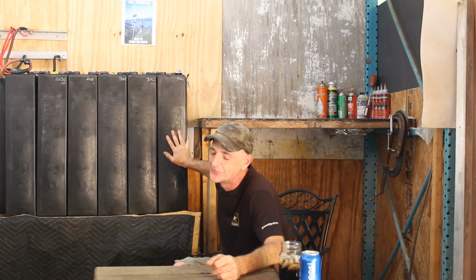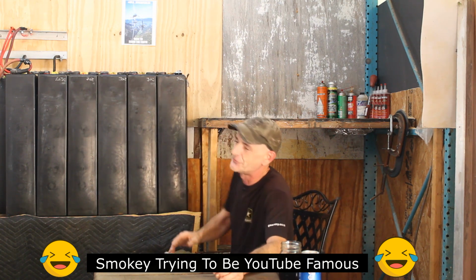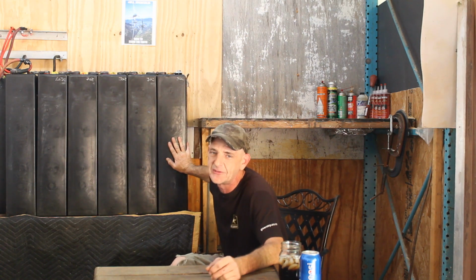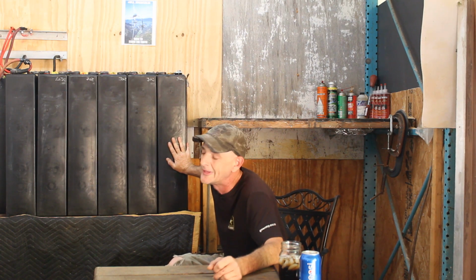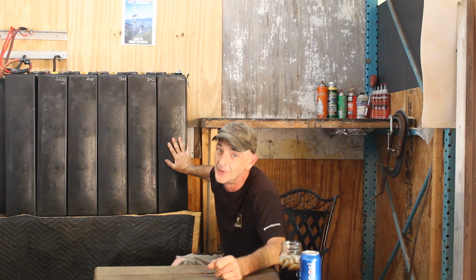These are the 20 amp, what's called a C20 rate, which is what the vast majority of solar batteries are rated at. A C20 rate, which is a 20-hour rate, not a 6-hour rate. So, what that means is, and this is why I'm saying you can use a degraded pack and you will never notice if it's down a little bit on capacity. The true rating on an 800 amp hour C6 pack in solar use, look, I don't know what the exact number is going to be, but it's going to be 1200 amp hours. Okay, it's going to be up there.